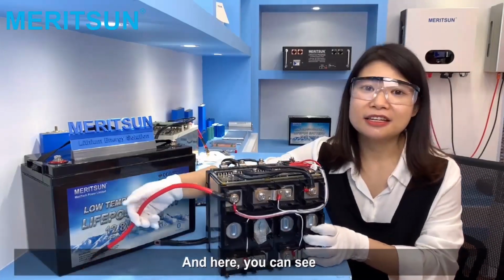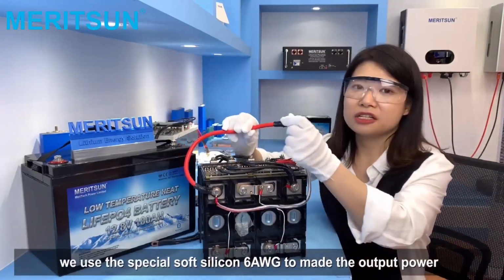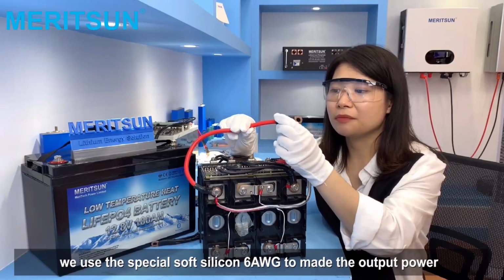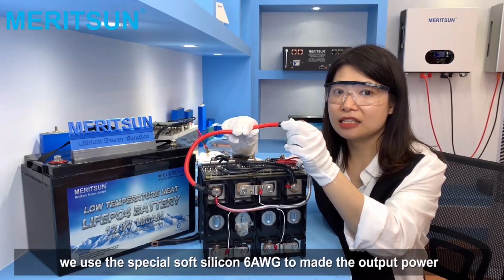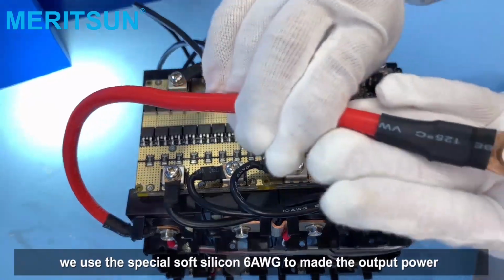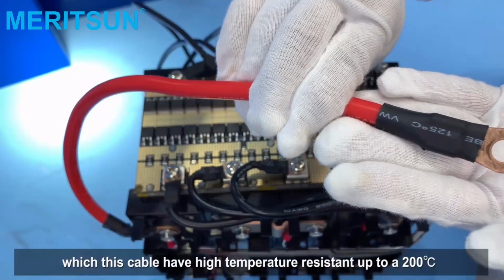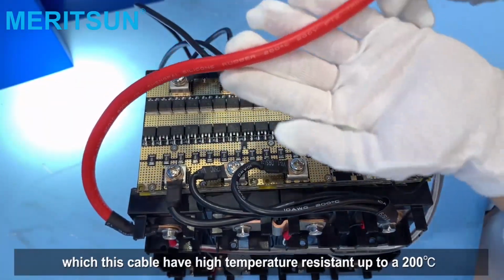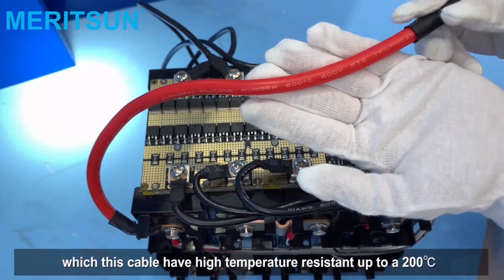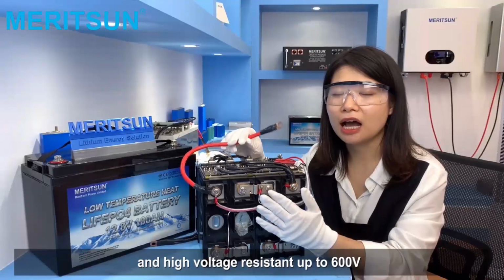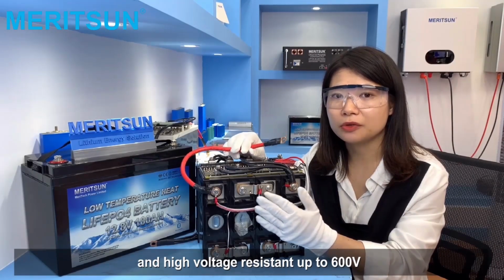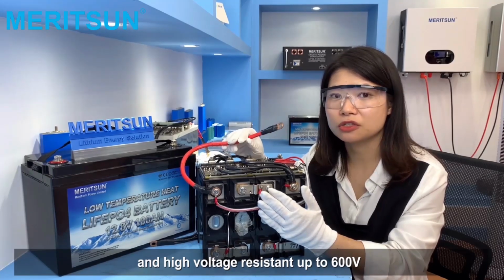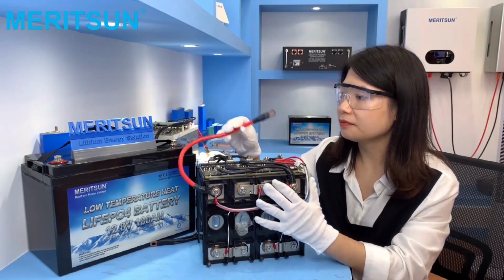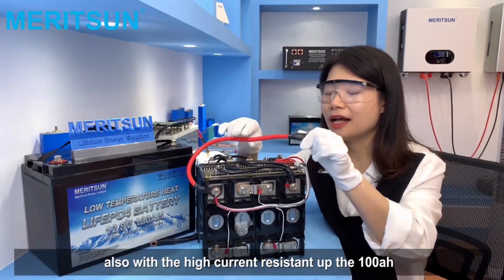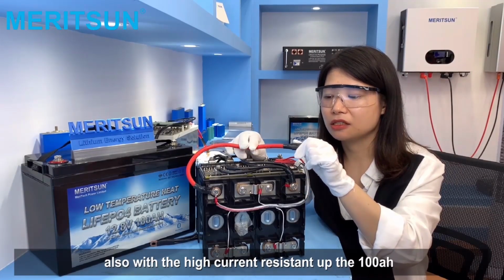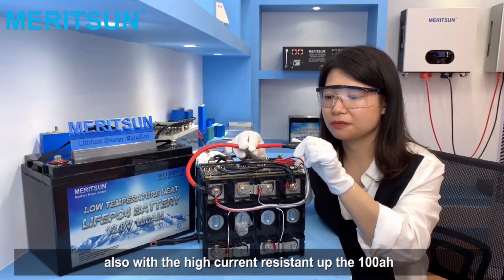Okay, and here you can see we used special soft silicone cables, 6 AWG, for our output power. These cables have high temperature resistance up to 200 degrees, high voltage resistance up to 600 volts, and high current resistance up to 100 amperes.